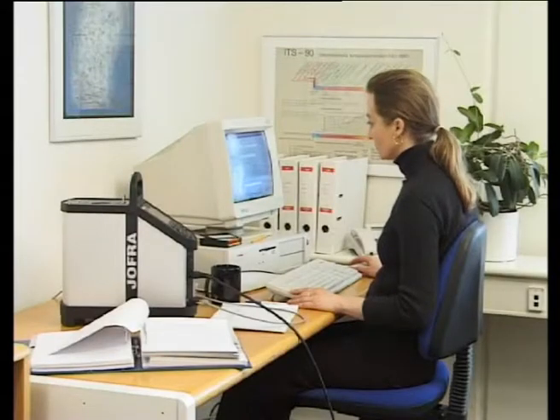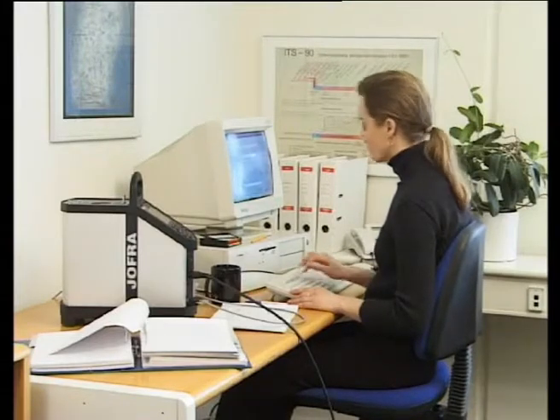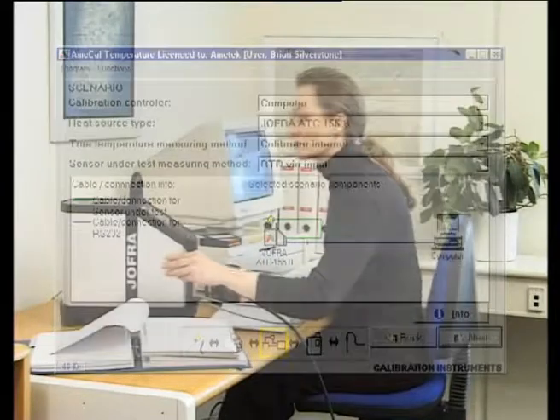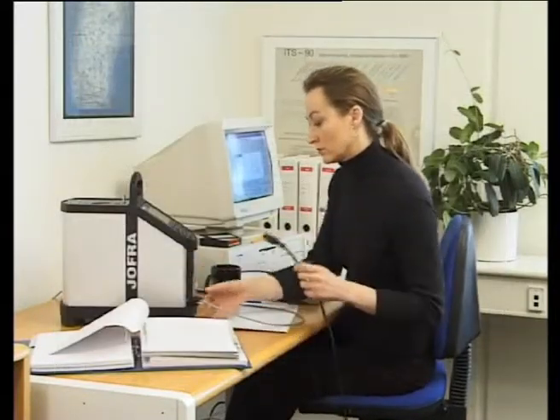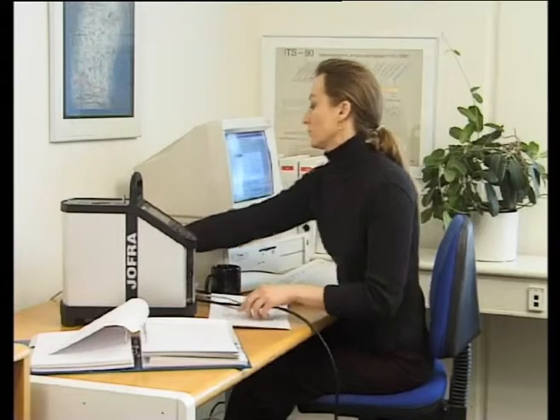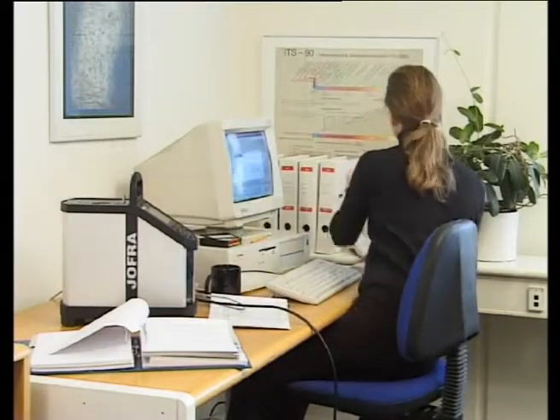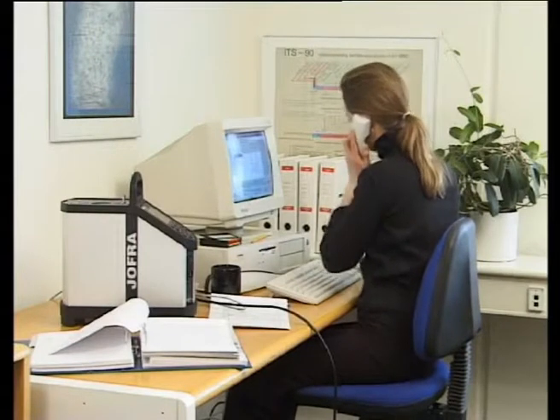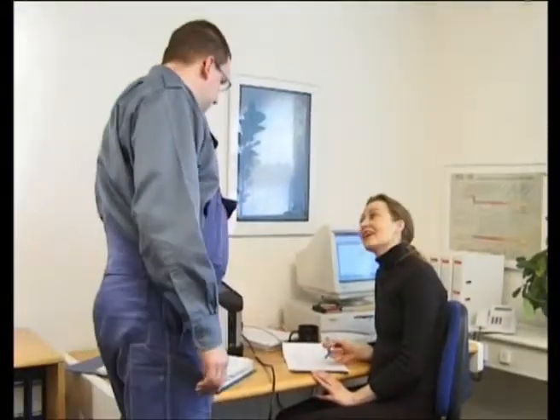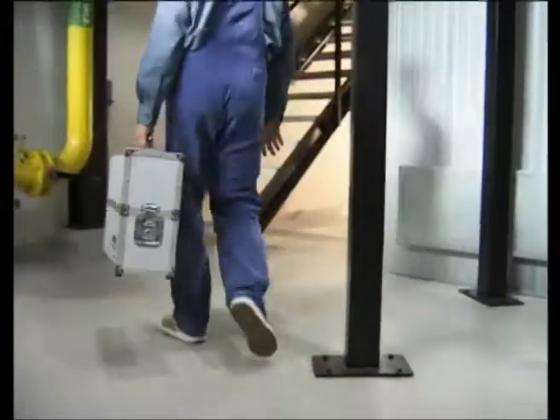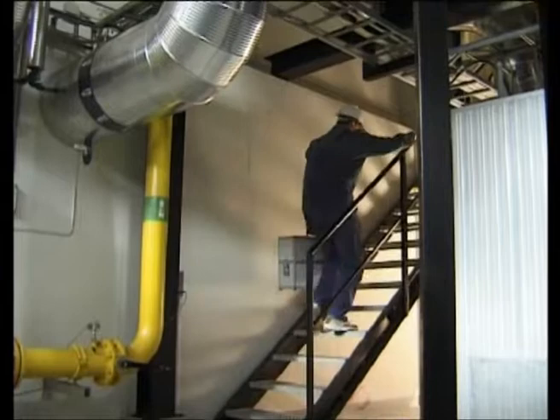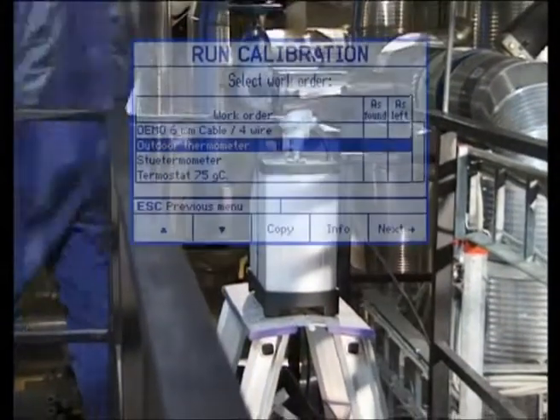You design all your calibrations in the AmeCal Temperature software. The relevant calibrations are collected together in work orders and downloaded to the calibrator via the RS-232 interface. The calibrator stores the calibration procedures and can be taken out to the process line without bringing the PC. This is beneficial to you from 2 standpoints. First, the JOFRA ATC calibrator is able to operate as a standalone calibrator using complex routines. Second, personnel who are not authorized to alter a calibration routine may operate the unit using a pre-programmed test sequence.